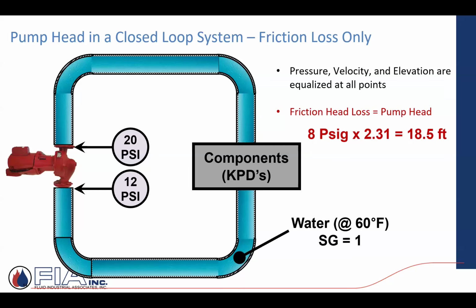Moving to the next drawing here, which they'd refer to as a closed loop, which I would imagine is a very high percentage of the systems you're going to be designing and working on currently and in the future, a closed loop system, where we're really just concerned with friction loss. So they make a statement over here: pressure, velocity, elevation are all equalized at all points. So I'm really concerned with calculating the friction head loss, which will then become my pump head. So I go back to that pump curve and I've established a certain flow rate based on BTU load, delta T, what's my temperature drop? There's my GPM. Now, as I move this GPM through this closed loop, it's obviously a very, very simple drawing, but that could be a building, it could be a makeup air coil, it could be whatever we want it to be. I have to calculate just the frictional resistance, which will then establish my required pump head. Then I can go select a circulator to meet those conditions.